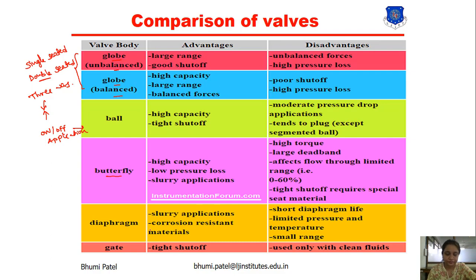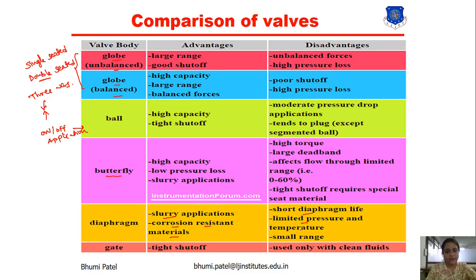The next is the diaphragm valve. We can use a diaphragm instead of ball or butterfly. One advantage is the overall cost of the valve is less. The disadvantage is short diaphragm life — if high pressure is applied, the diaphragm will be damaged compared to butterfly or ball valves. Advantages include suitability for slurry service and corrosion resistance. Disadvantages include short diaphragm life, and limited pressure and temperature range.